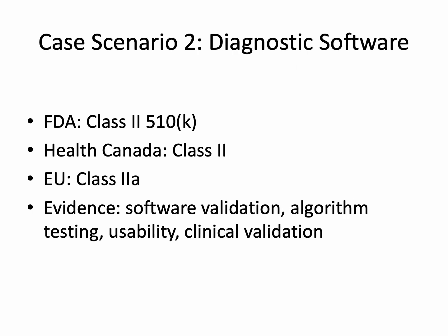AI-based medical image analysis software presents unique regulatory challenges. FDA Class 2 requires 510(k) submission with special controls, Health Canada Class 2 requires MDL with supporting evidence, EU Class IIA requires notified body assessment.